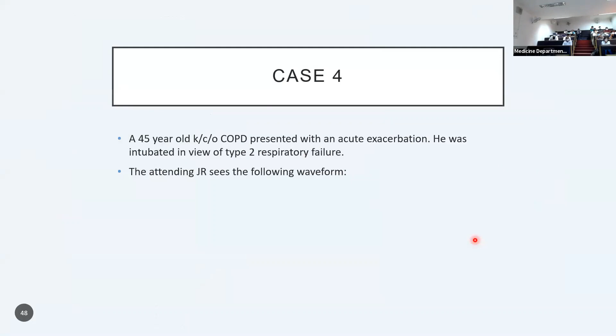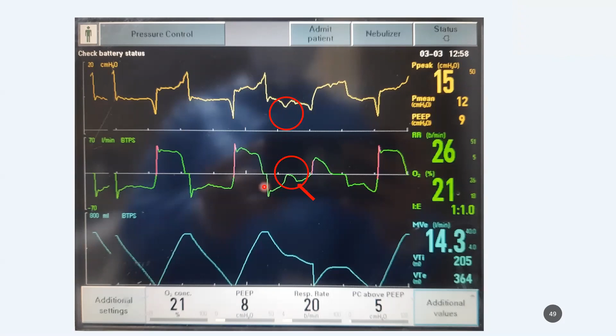As I said, flow towards the patient from the ventilator is a positive deflection, and flow from the patient to the ventilator is expiration. So during expiration, what we can see is a positive deflection, that the air is trying to move from the ventilator to the patient. Simultaneously, there's a drop in the pressure, that the patient wants to inspire air. So this is an ineffective trigger: the patient wants to trigger a breath here, which is manifested in this wave, but the ventilator is not giving a breath.